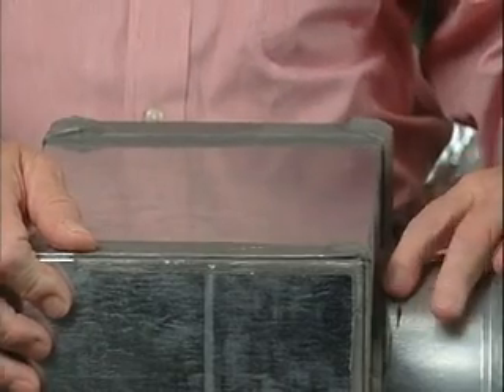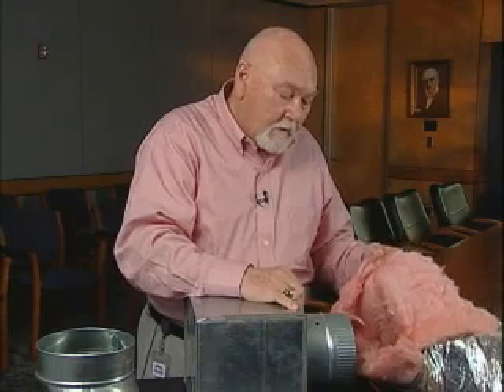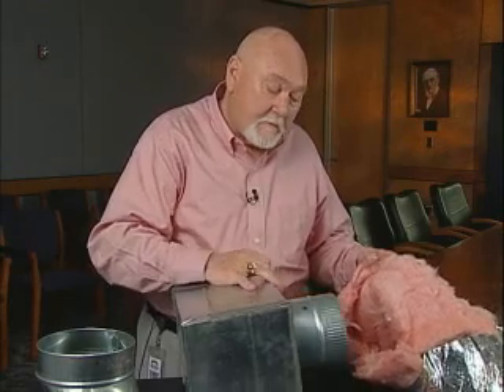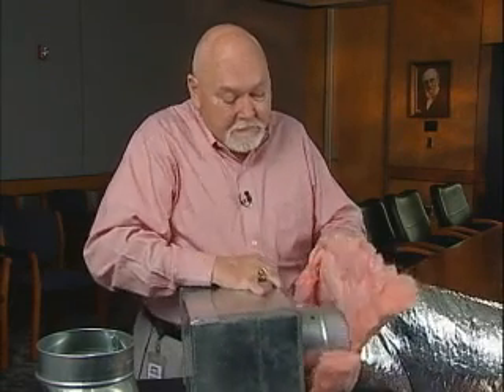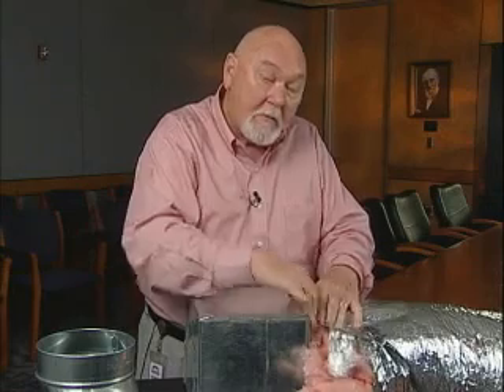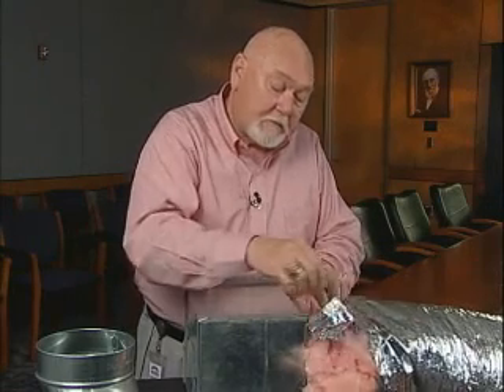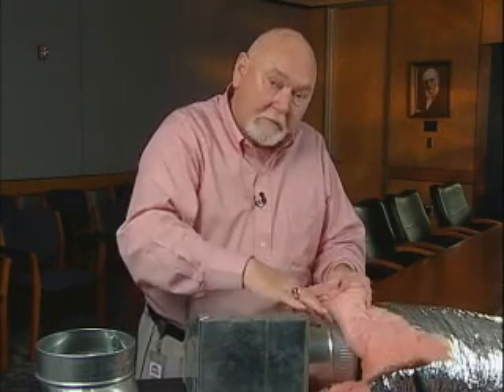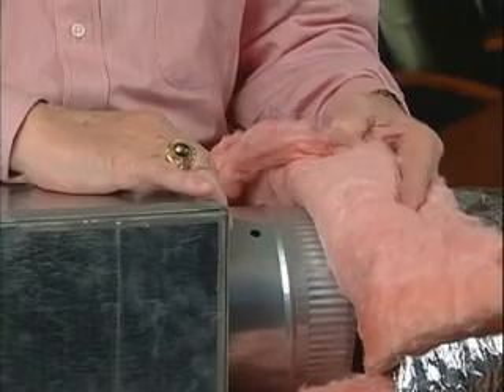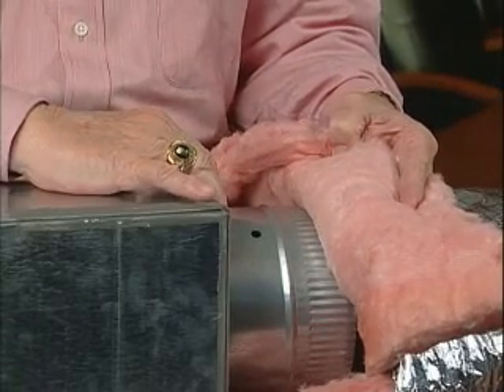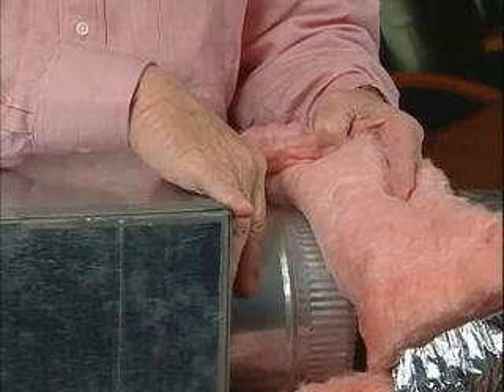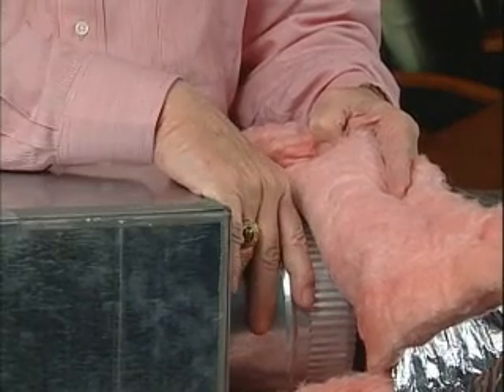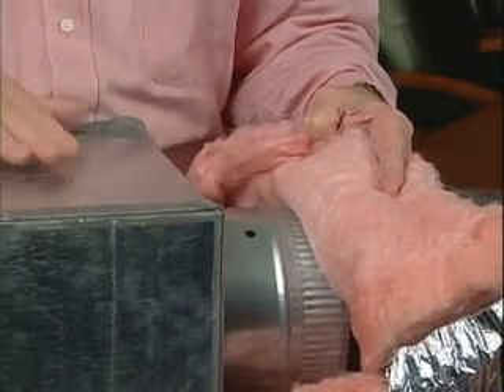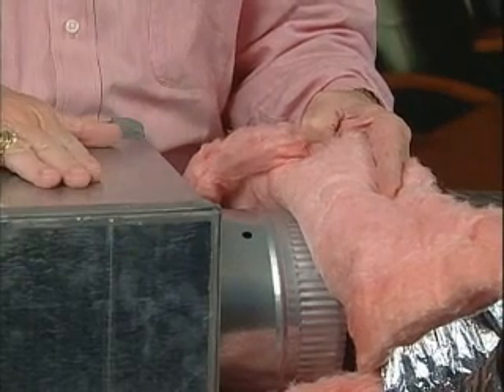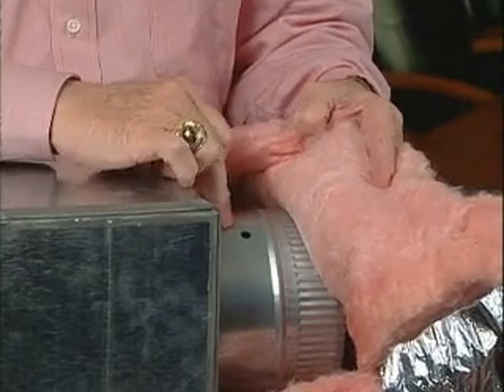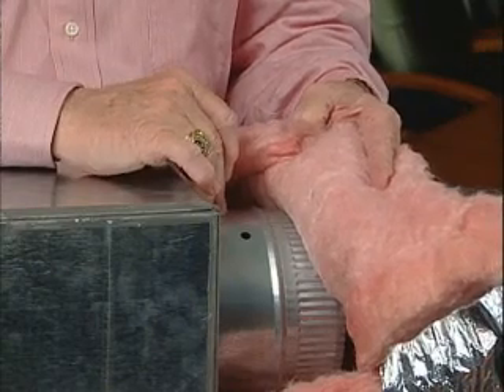At your takeoff right here, that's sealed. Where the ductwork attaches to the metal takeoff, it fits on like this. There's a membrane in this ductwork that is pulled tight over this metal. You want to pull the membrane down across this metal takeoff, and you want to apply mastic to that. That way you have a seal of where the air is being driven up this main supply into this takeoff, and there's no way that it can suck air here.